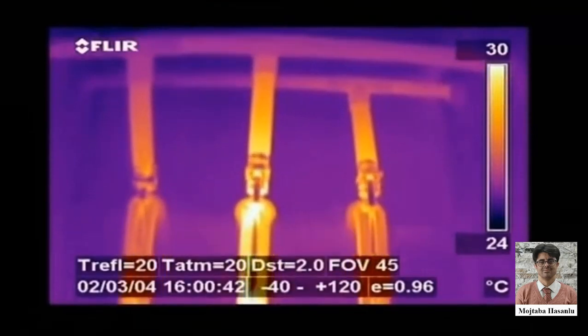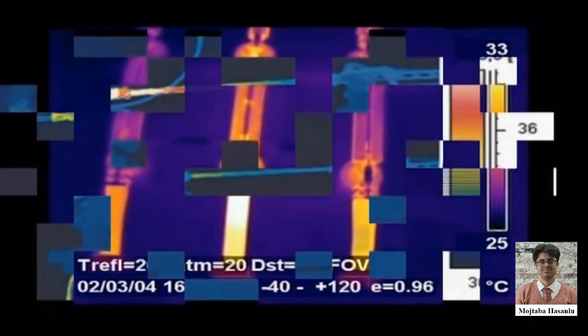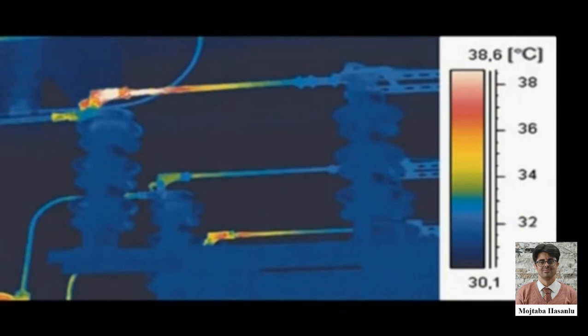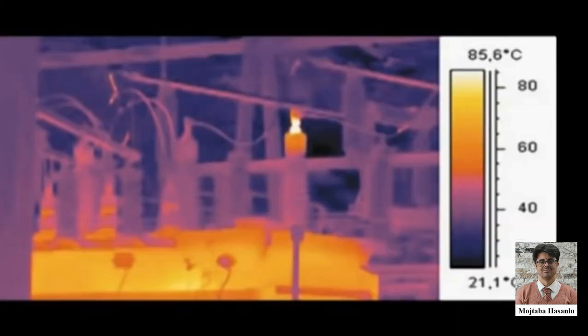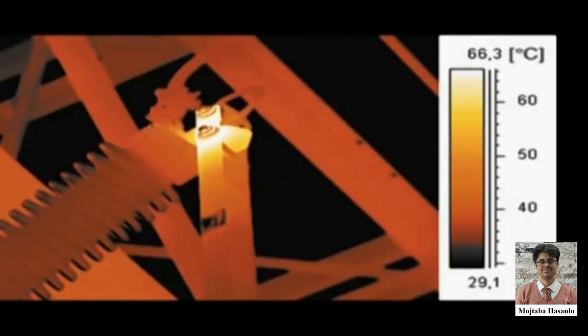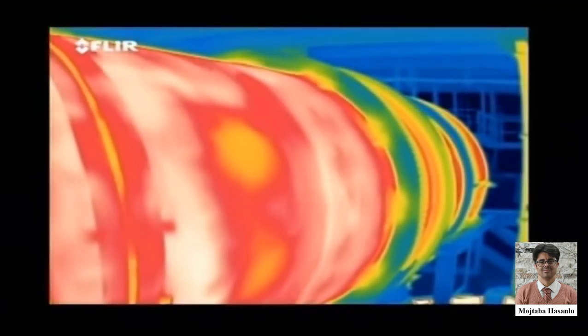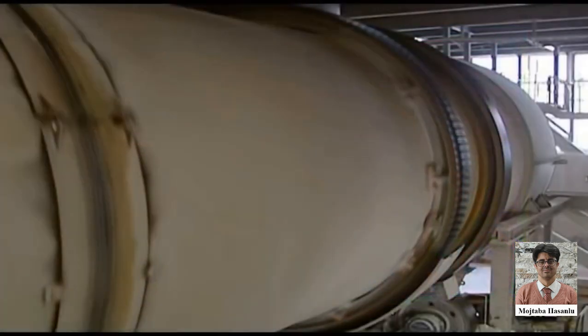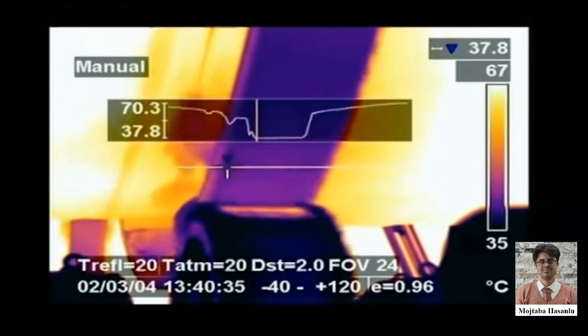Examples of failures in high voltage installations are oxidation of high voltage switches, overheated connections, incorrectly secured connections, insulator defects. In many industries, mechanical systems serve as the backbone of operations. Thermal data can be an invaluable source of complementary information to vibration studies in mechanical equipment monitoring. Mechanical systems will heat up if there's a misalignment at some point in the system. Thanks to features such as line profiles, you will immediately see if there's a problem.